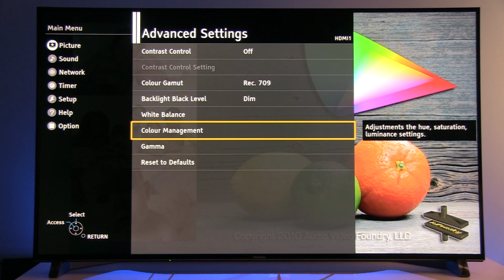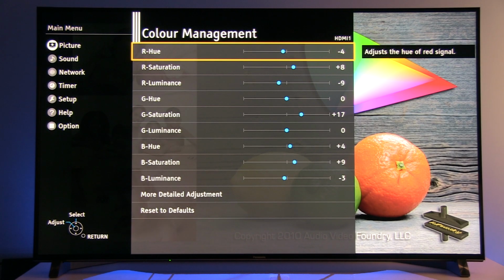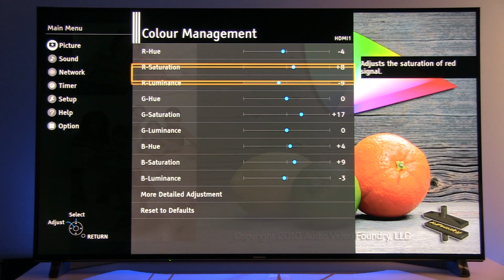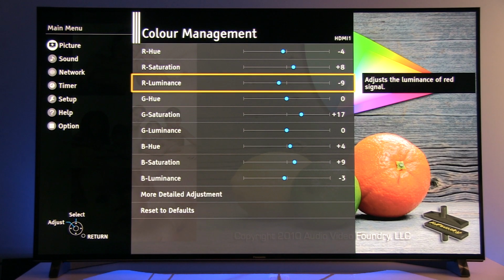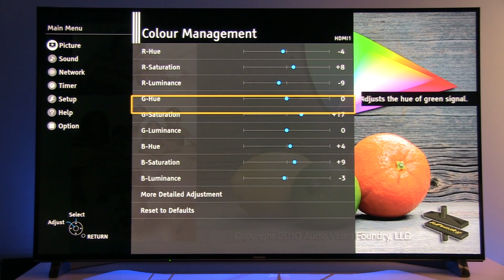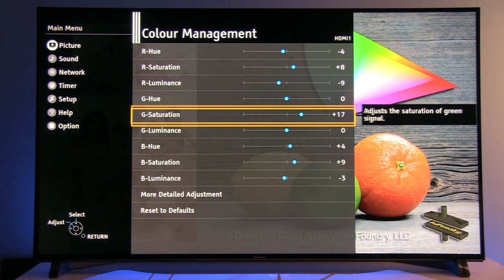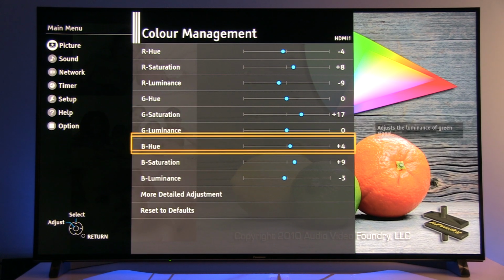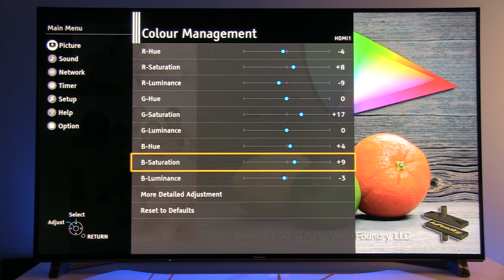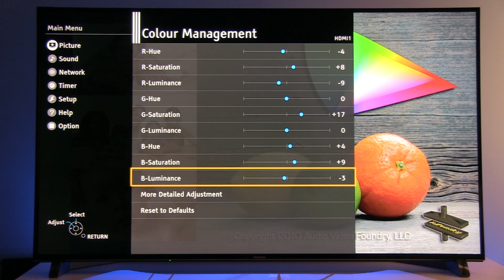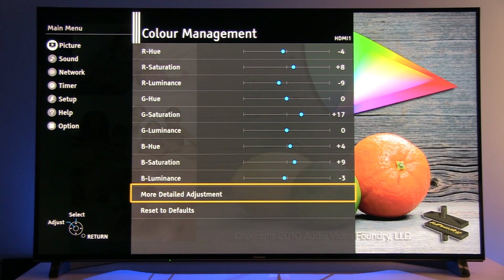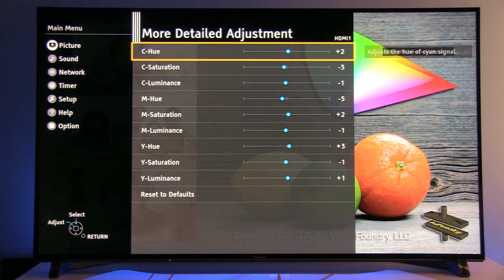Okay, now let's go to color management system, where you see that for primary and secondary colors, auto calibration did these adjustments. Red hue -4, red saturation +8, red luminance -9, green hue 0, green saturation +17, green luminance 0, blue hue +4, blue saturation +9, blue luminance -3, and now let's see secondary colors.